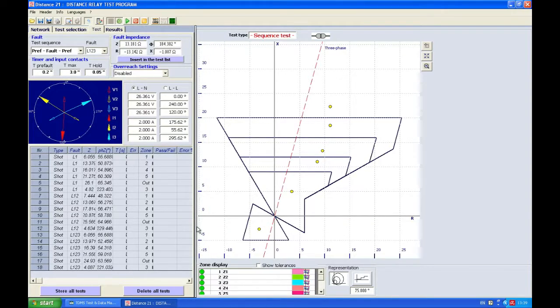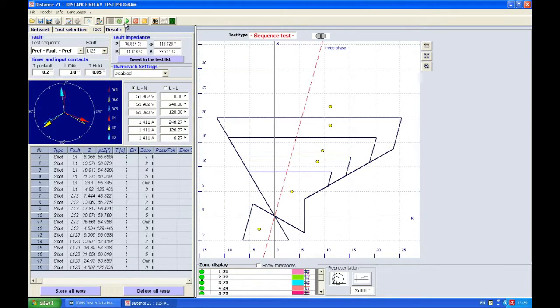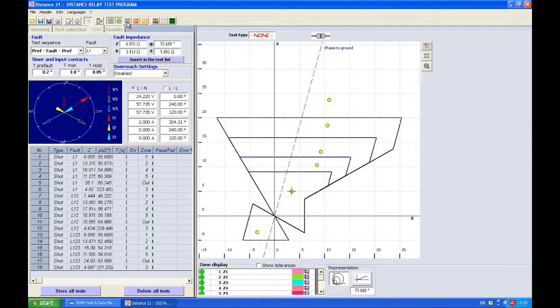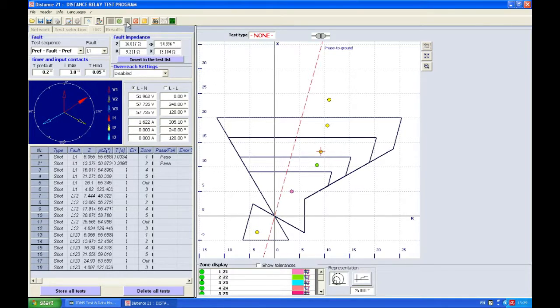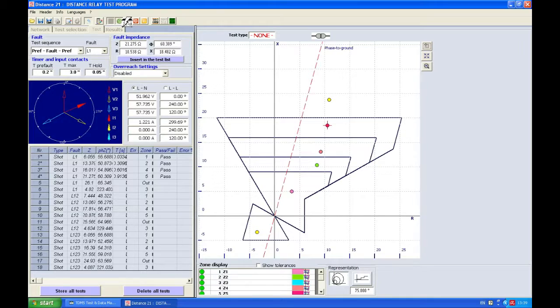In order to start the test, of course we're going to press start and we will see how this test is being done. Right now the DRTS in sequence is generating currents and voltages which of course make this type of impedance as you can see here.